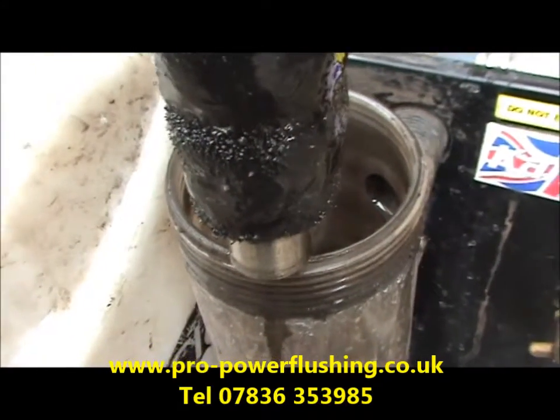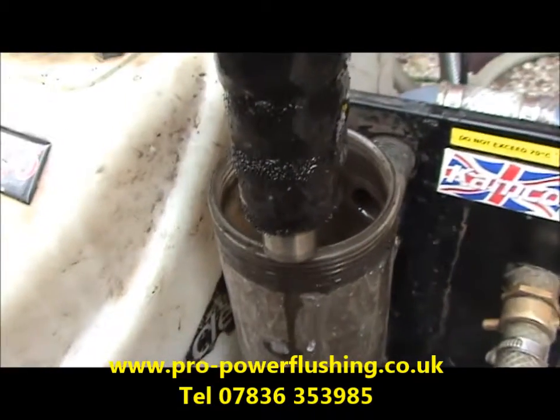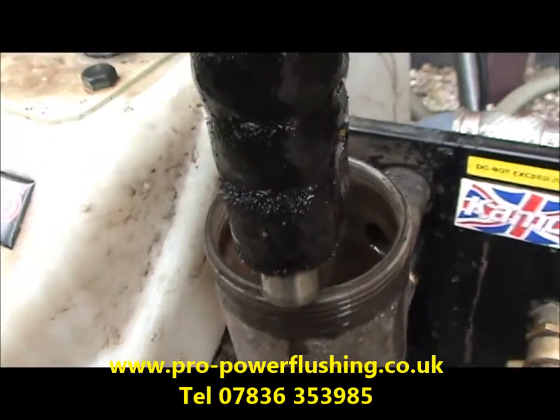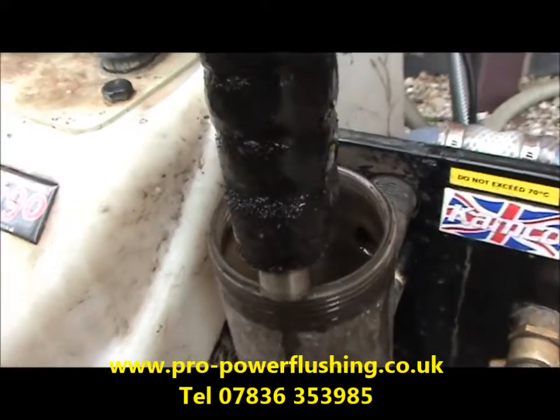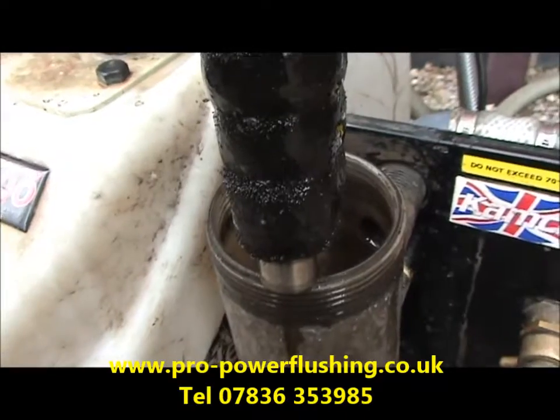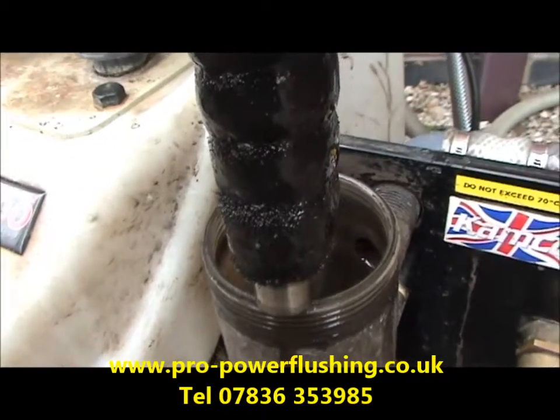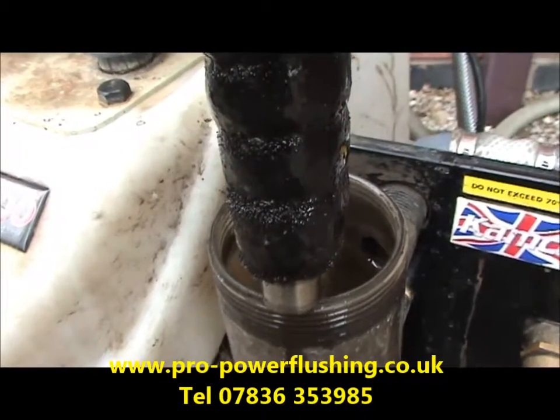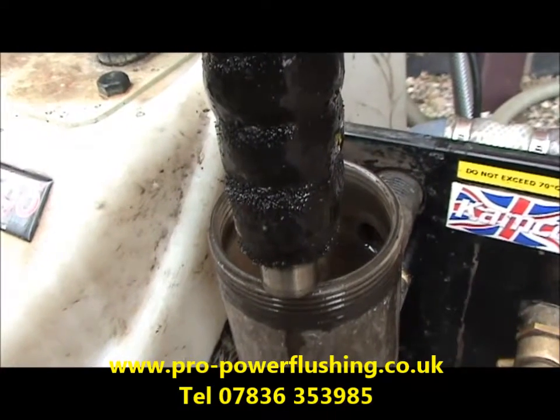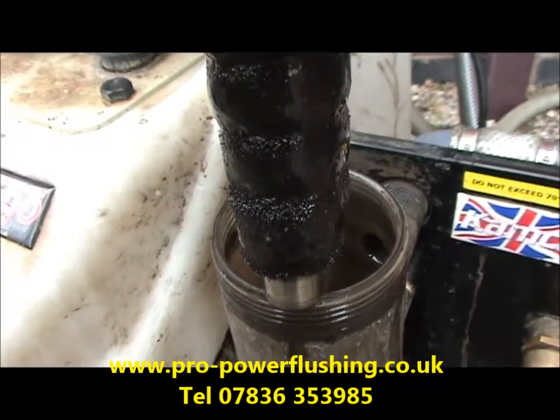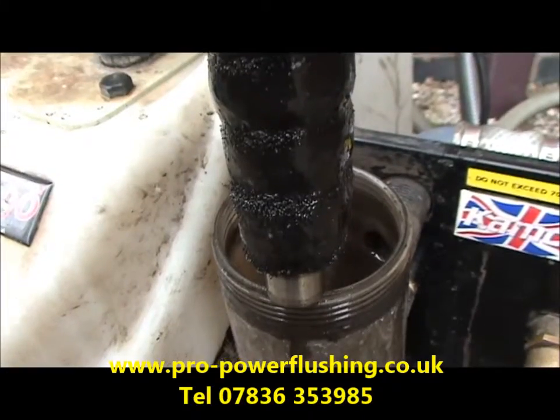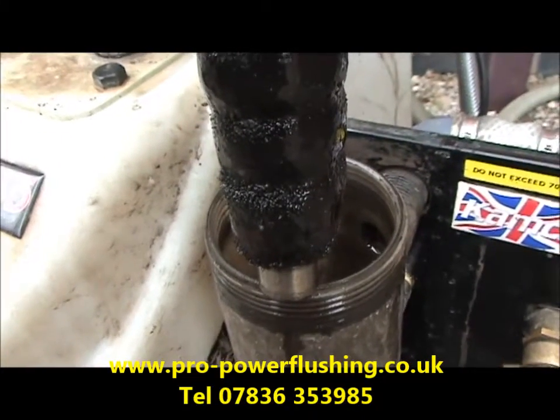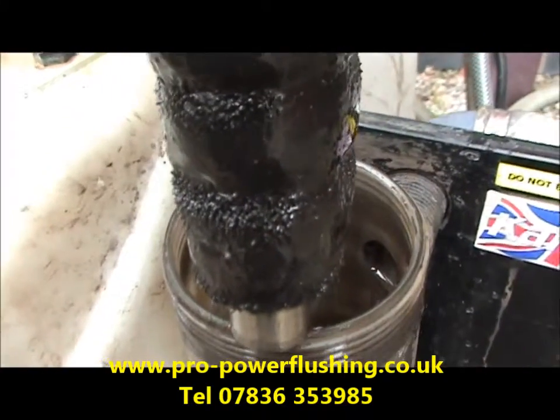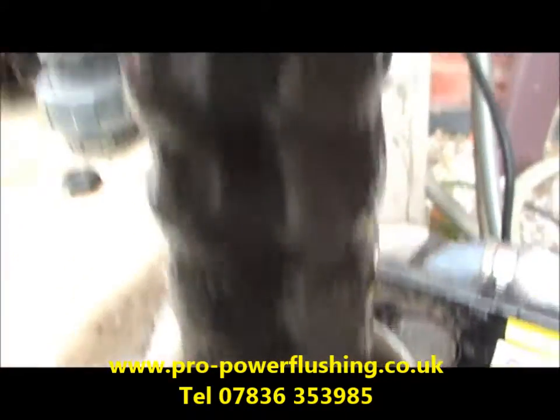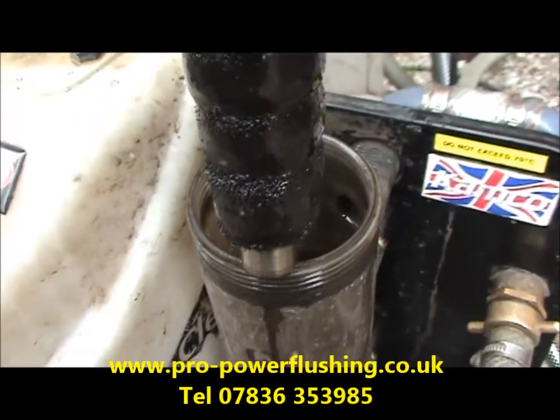This is what power flushing is all about. Imagine that going through your new boiler, or any boiler for that matter, especially combination boilers with small plate heat exchangers, or the coiled heat exchangers. They're not very large inside the new heat exchangers now. Through your pump, your valves, your flow sensors, flow switches, etc, eventually it's just going to wreck it. If you don't get this stuff out of your central heating system, the damage it can do is quite unbelievable. It can just write your boiler off, basically.